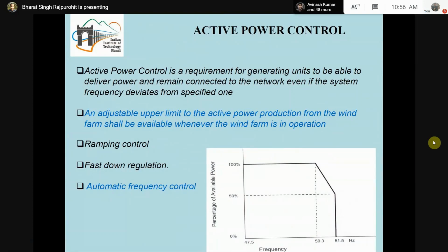How are we able to control it? If the wind speed is changing, the output of the wind turbine, the wind energy conversion system, is also changing. It means the output power coming from a wind farm or a wind generator can be controlled remotely in certain manners. The first one is known as ramping control. Ramping control means that if the wind changes from 0 meters per second to 12 meters per second very quickly, we should not operate our wind farm with such a sudden increase. That's why the grid code says there is a ramp increase, and that ramp should be followed rather than a very fast increase.